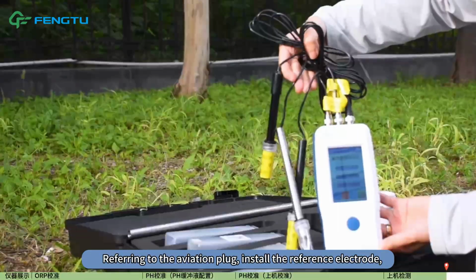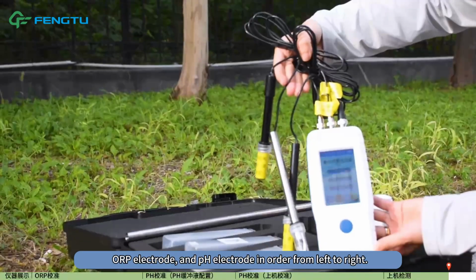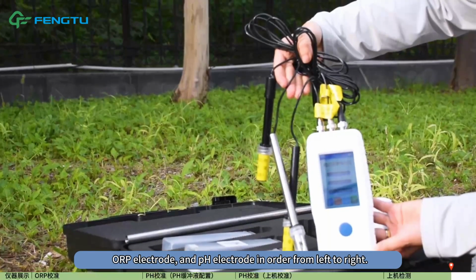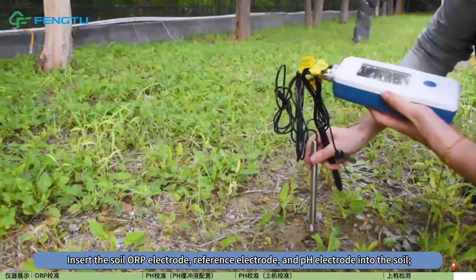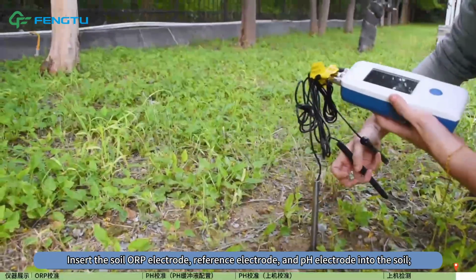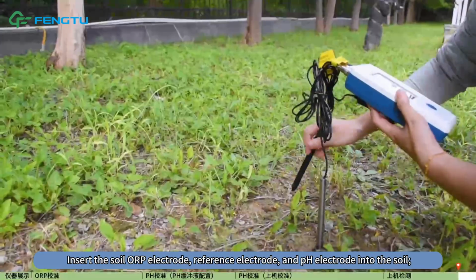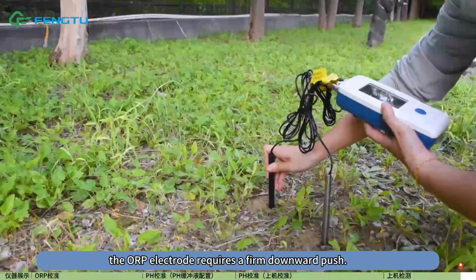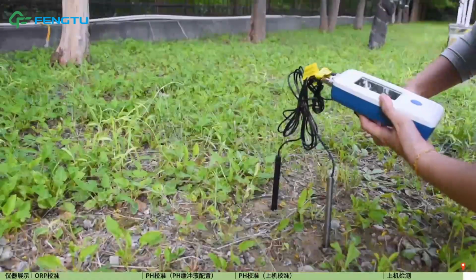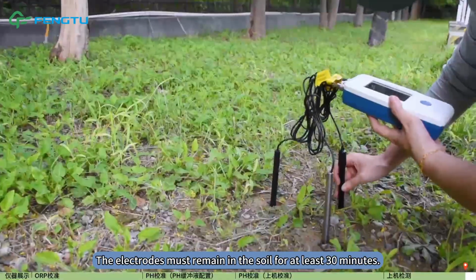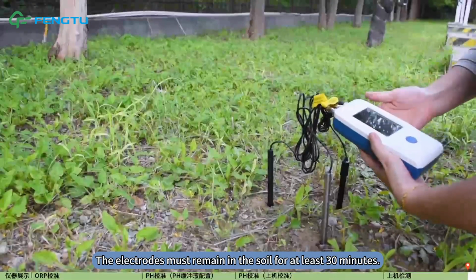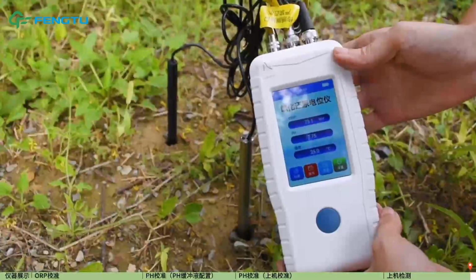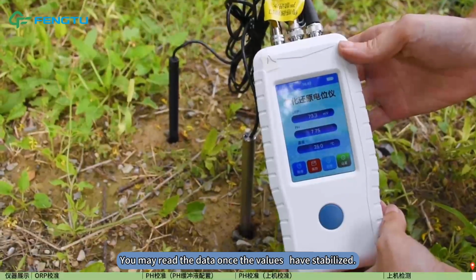Referring to the aviation plug, install the reference electrode, ORP electrode, and pH electrode in order from left to right. Insert the soil ORP electrode, reference electrode, and pH electrode into the soil. The ORP electrode requires a firm downward push. The electrodes must remain in the soil for at least 30 minutes. You may read the data once the values have stabilized.